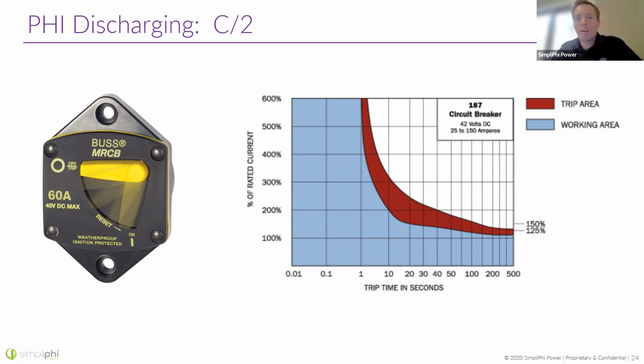So this breaker comes with a specifications diagram, right? And notice that if we look at the rated current of this breaker, 60 amps, and we look at going at 60 amps, this breaker will actually pass 60 amps continuously, right? It's a weatherproof outdoor rated breaker at 60 amps. And if you pass 60 amps through the breaker, it's not even going to trip. So where does it trip? When you get a little bit above 60 amps, it can trip.